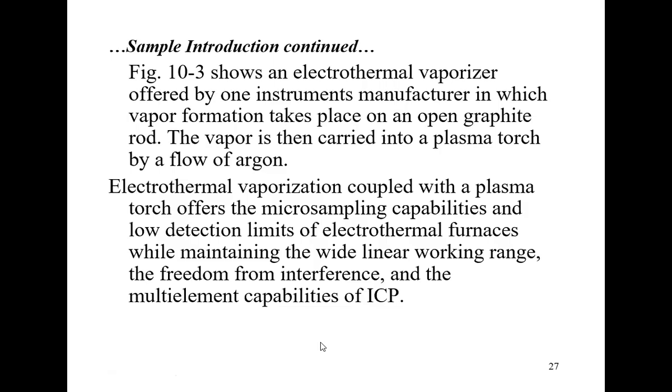So electrothermal, again, you can imagine if you're going to do the electrothermal type of introduction, if you use a graphite furnace, you have to couple it in such a way that you have the furnace coupled to the nebulizer, just like what we do in AA.